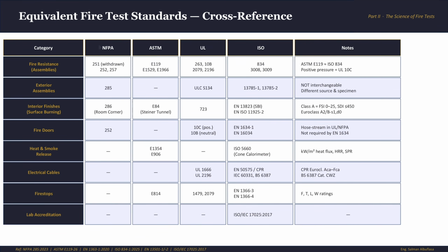This table is a simple idea for cross-reference. You might have the same category by different test methods. Some are similar and some very different from each other. For example, the ASTM E119 and the European equivalent 834 are similar to each other. But for the interior finishes, ASTM E84 is very different from the SBI 13823. They're not equivalent to each other and they're not interchangeable. So make sure you do not substitute one for the other.